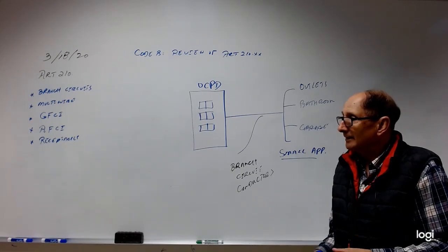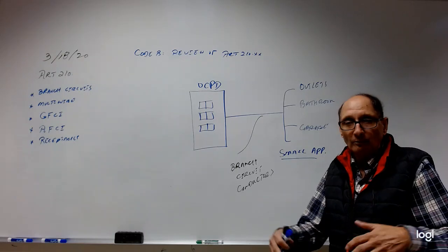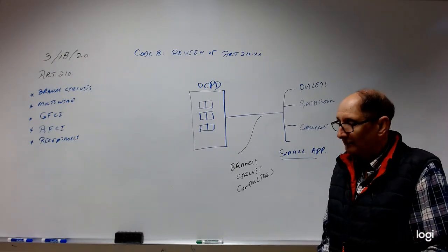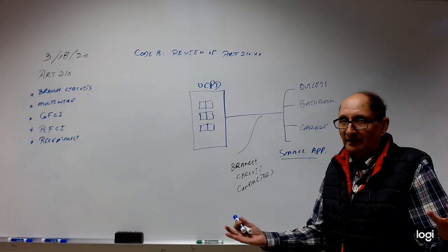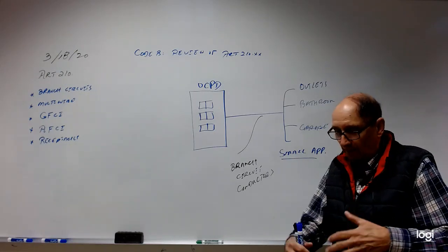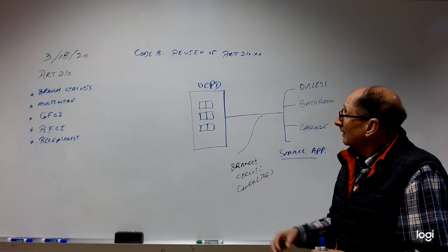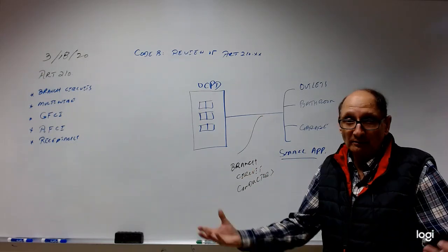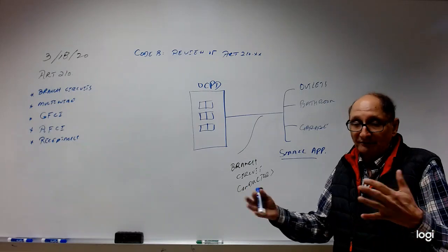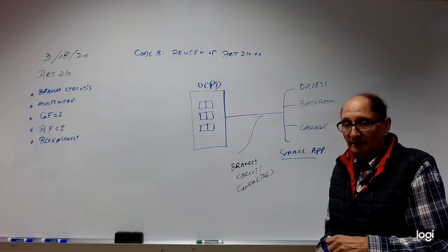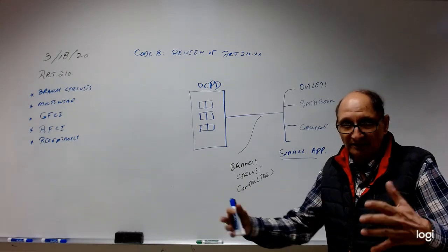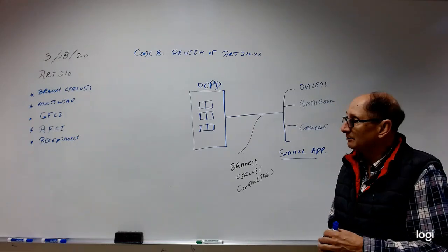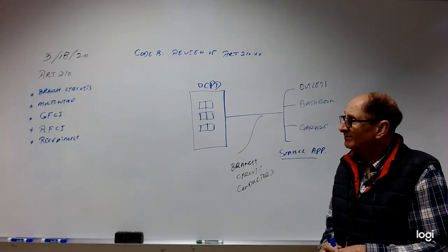But when it comes to overcurrent protection, a GFCI is not an overcurrent protection device. As you may know from the previous classes, a difference in current between line in and out of anywhere between 4 to 6 milliamps basically pops it open.